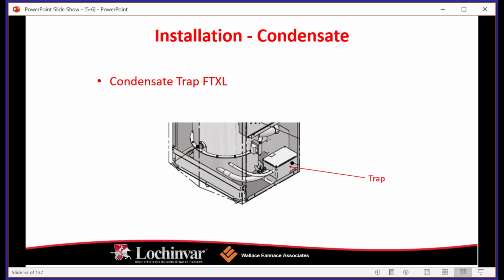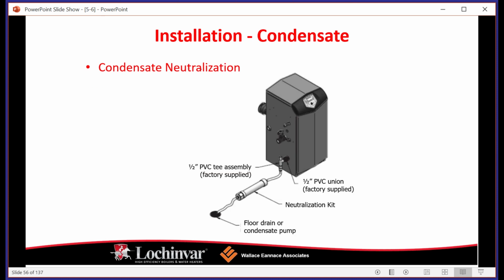On an FTXL, the trap is located in the rear of the cabinet. It is integral. So we need to capture that condensate and expel it from the boiler. People are often surprised at how much condensate a boiler can make. At about 100,000 BTUs in condensing mode, you're going to get about a gallon of condensate per hour.